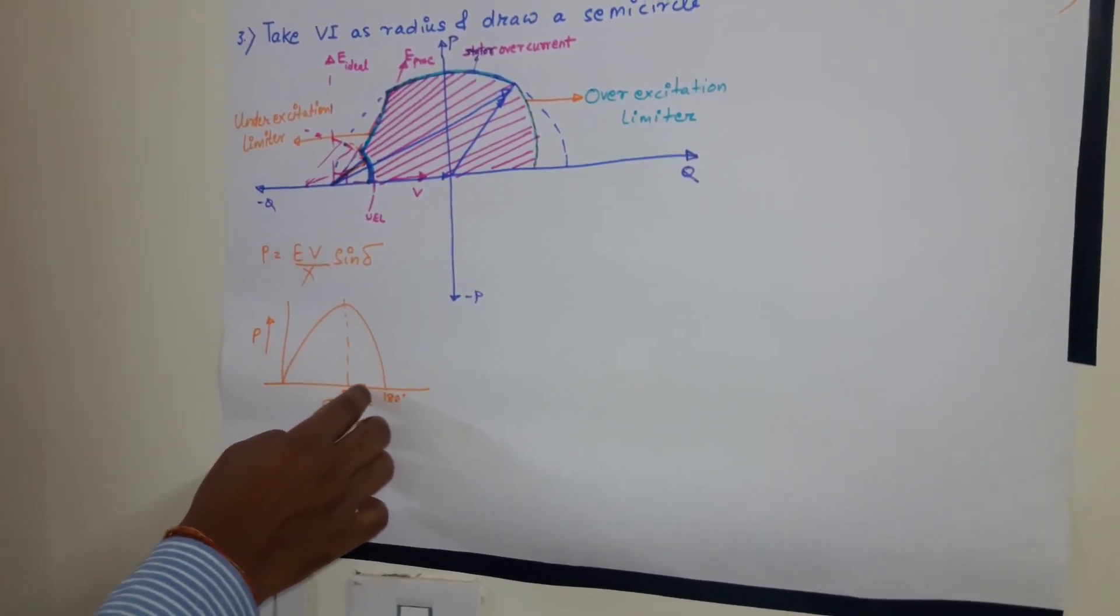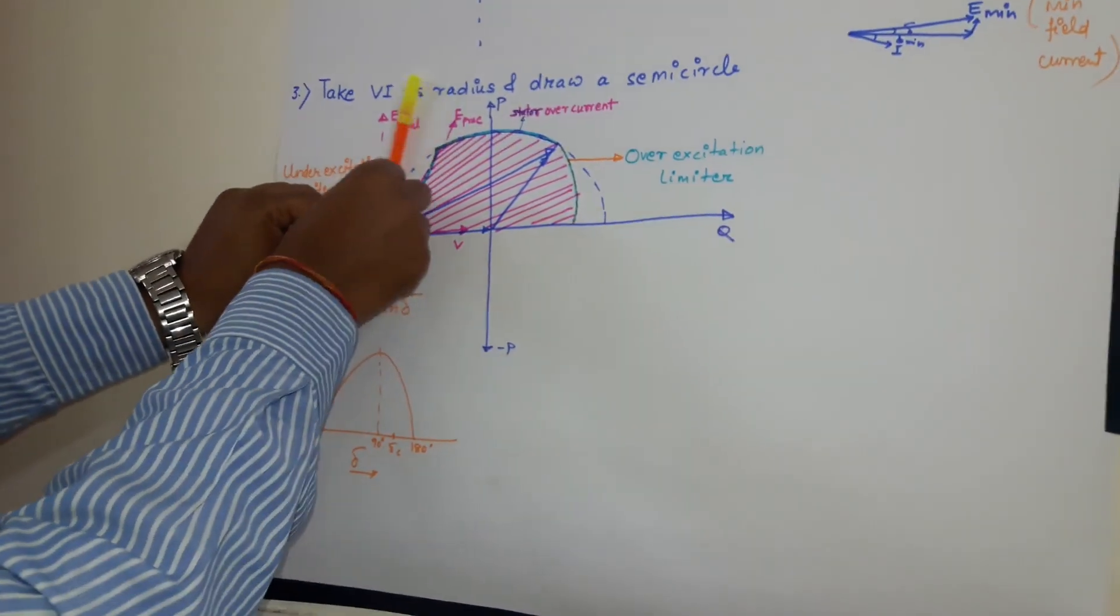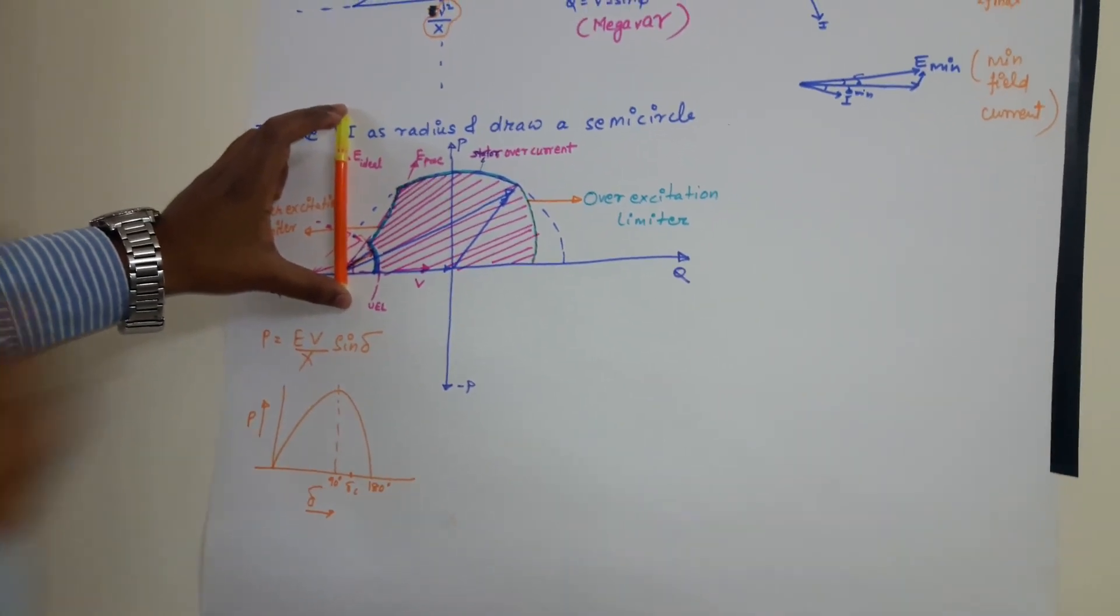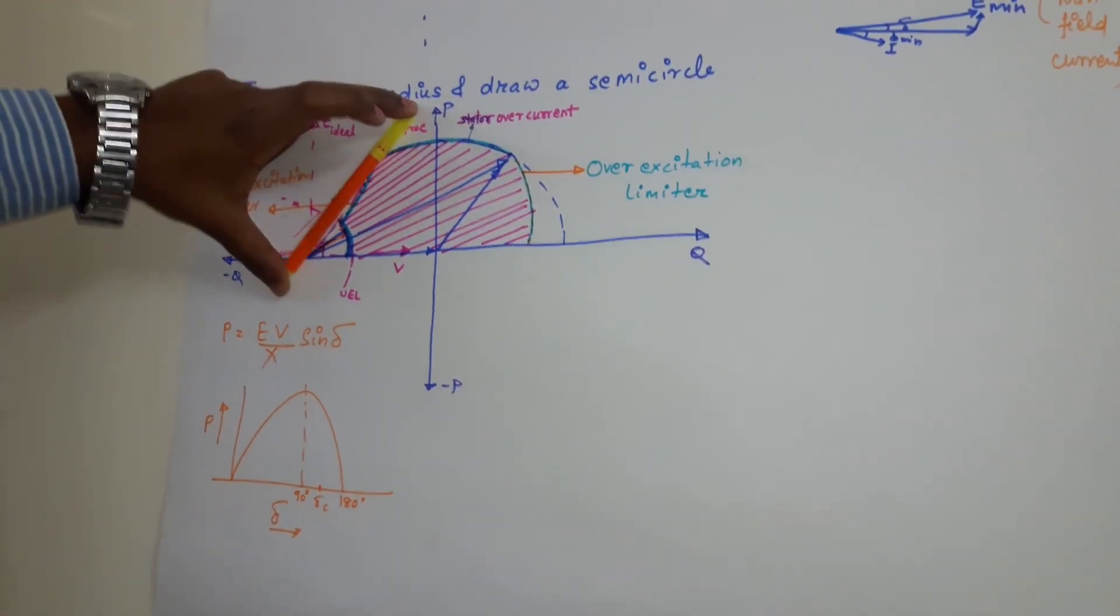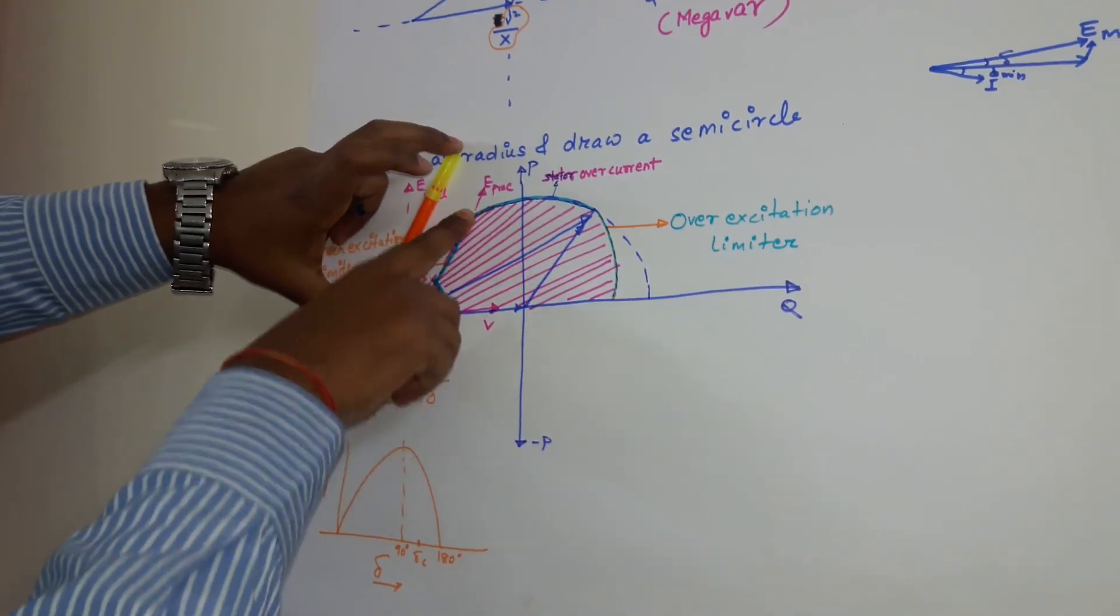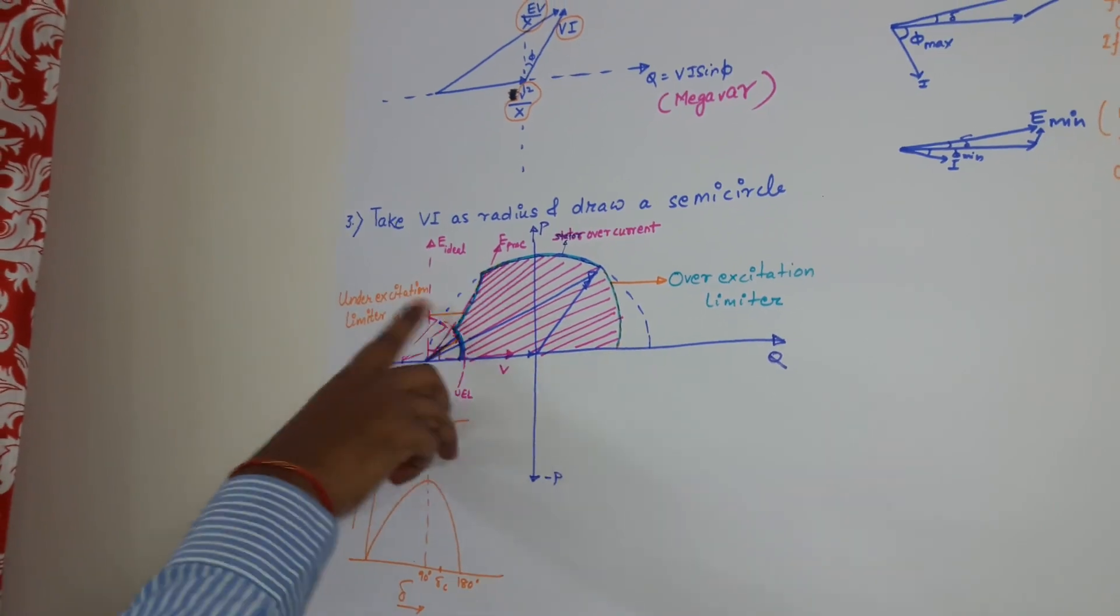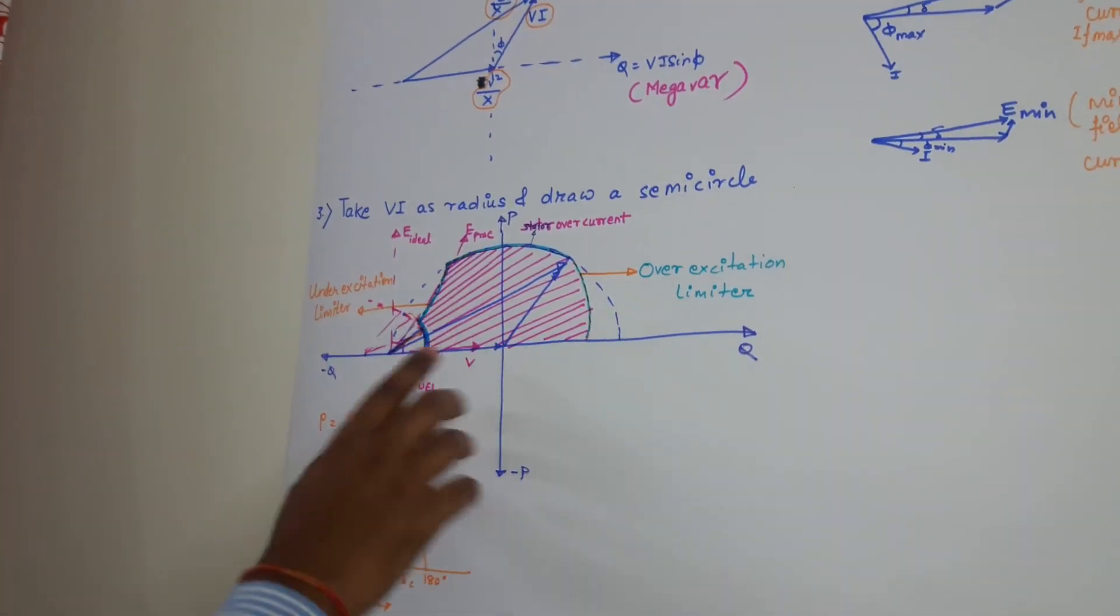So if this is V, generator can operate in a smooth manner up to this point. But this is ideal line. What is the practical line? It is somehow lesser than the 90 degree. So this is the safe zone for generator to operate. So we are also getting this load angle limiter line, which is also coming under under excitation limiter.